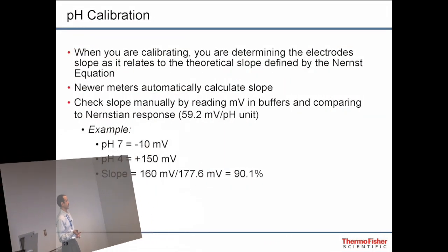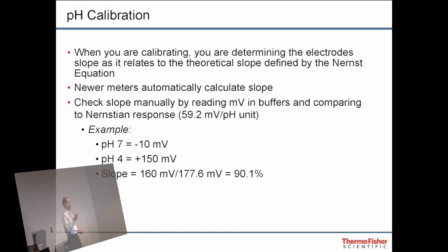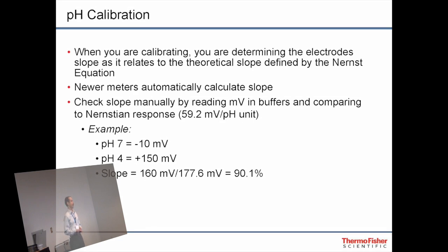And that's what the meter does for you. Most of your meters, I'm sure, give you a slope after you calibrate: 98%, 99%, 92%, whatever. What the meter is doing internally is looking at the millivolt values for those buffers. Let's say you take your electrode and put it into a pH 7 buffer. That pH 7 buffer on the millivolt scale, if you switch your meter to the millivolt scale, is reading negative 10, let's say. Should be pretty close to zero.